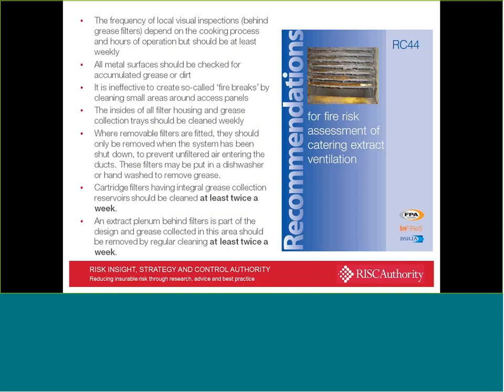But anybody who is familiar with the dynamics of fire will understand very quickly that it's not necessarily the fact that a material is impacted by a flame that causes it to ignite. Every material has an auto ignition temperature, and greases and fats are no different, and in general terms will have quite low auto ignition temperatures compared to other types of material. And so that sort of approach to cleaning is going to be completely ineffective.